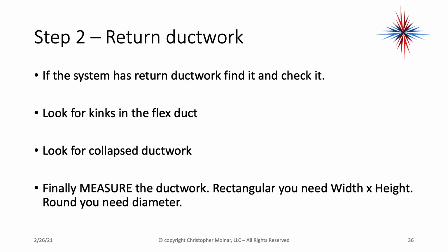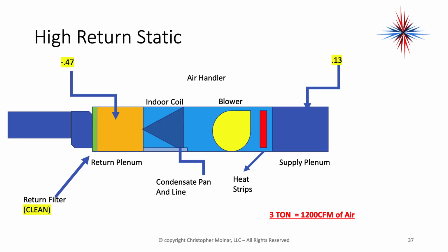If the system has return ductwork, find it and check it. Look for kinks in the flex duct. Look for collapsed ductwork. Finally, measure the ductwork. Rectangular, you need width times height. Round, you need diameter. Again, we have a 3-ton system, need 1200 CFM of air. And the ductwork we want to measure is my return ductwork, which is, oops, let me go back, this area to the left of the return plenum. You also want to look for restrictions.